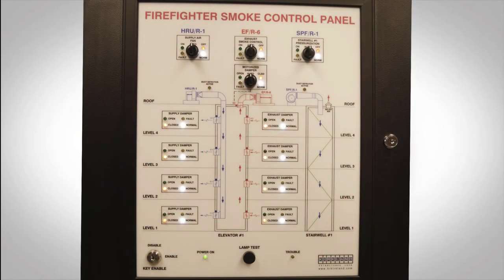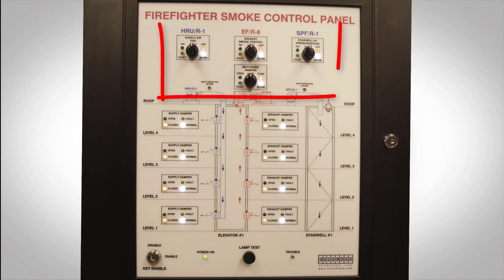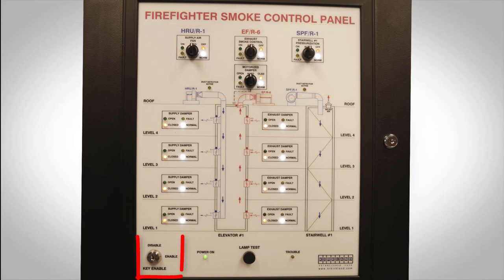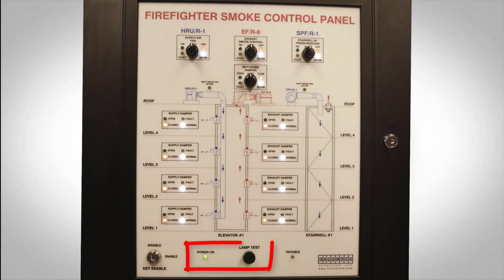A smoke control system will also consist of a firefighter's smoke control station — a standalone cabinet containing a graphical representation of the smoke control system, three-position switches for manual control of fans and dampers, a manual control enable switch, fan and damper status LEDs, lamp tests, and a smoke control station power LED.